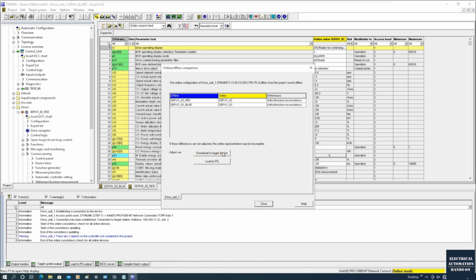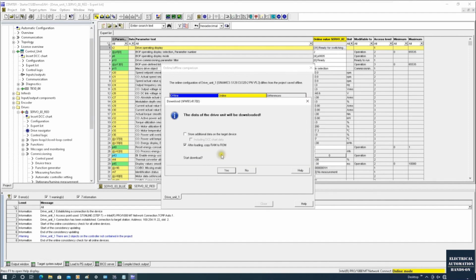And make sure every time we download, you must think very clearly before you change something from your offline project. You need to click this load to PG. Make sure all the online has been uploaded. And then you change from the offline project and download to the online device again. Otherwise, if your offline project is not updated yet, and then you change the offline, then download to the drive, it will override something and maybe some parameters you set while doing the online commissioning will be lost forever. Okay, so let's click this download. Make sure you upload first, do the offline change, and then click this download to device.